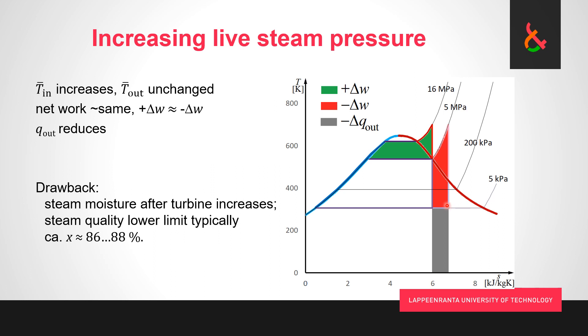Moving toward the world of real power plants: between the saturated liquid and saturated vapor lines we have wet steam, and the further left we go, the more liquid droplets we have in the steam. By moving deeper into the wet steam region, there are more droplets, and if we had a real turbine there, its last stages would be bombarded by a greater amount of water droplets, causing greater erosion and shortening the turbine's lifespan. So going too deep into the wet steam region is a bad thing.